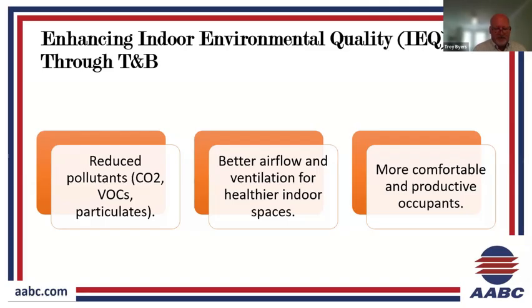We went through a big shift in the way buildings were set up when we went through COVID. ASHRAE formed an epidemic task force with a lot of guidelines that came into play, and a lot of buildings' HVAC systems were changed, modified. And so we've got existing buildings today that need to be brought back out of that, or maybe some hybrid of the previous settings and what we actually need today. Again, occupancy has changed in buildings a lot, and that continues to change. So a periodic review of the test and balance is very important.